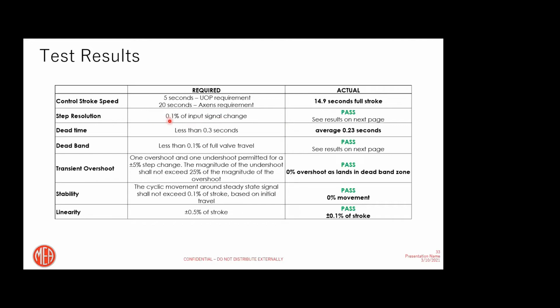Step resolution, 0.1% of input signal change. It passed. We will have the next set of results on the next page. Dead time, less than 0.3 seconds. This one averaged about 0.23 seconds, also pass. Dead band, less than 0.1% of the full valve travel, also pass. See the results on the next page. Transient overshoot, we completely pass it, 0% overshoot, landing in the dead zone every time. Stability, as you can understand, this would more apply to a servo valve type of HPCU system, to keep it stable. This unit, whenever it repositions to the final destination, just stays there until you command it to move. So 0% movement.